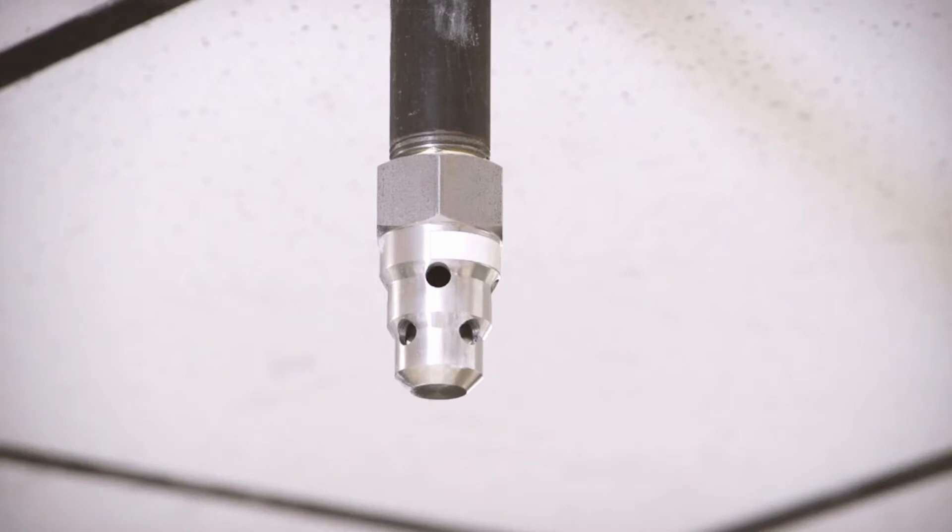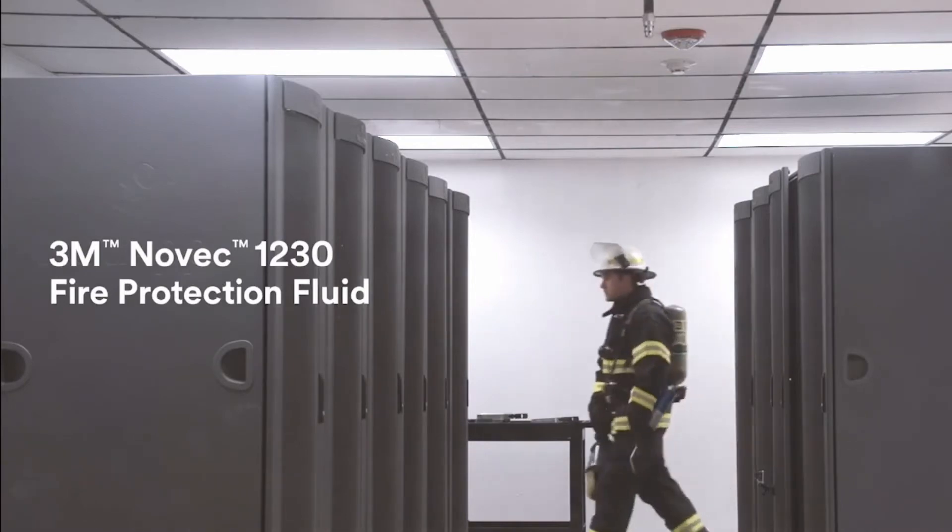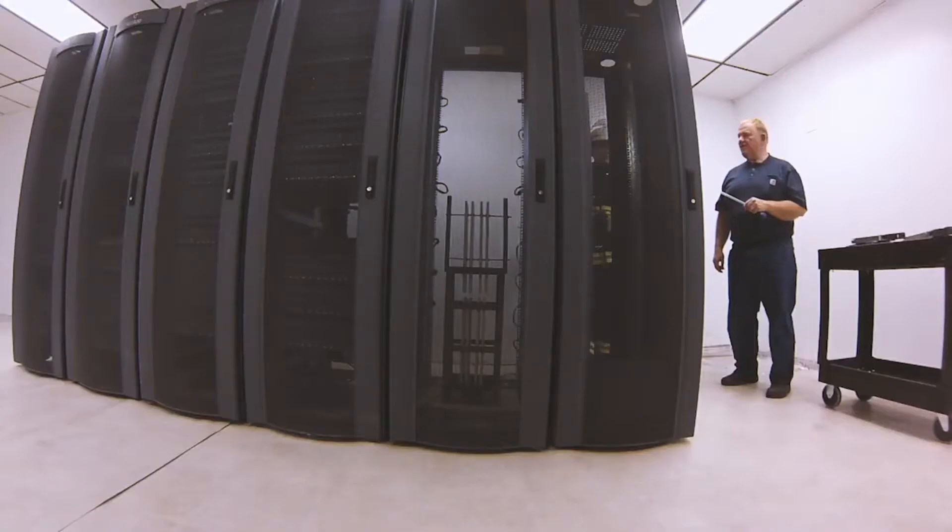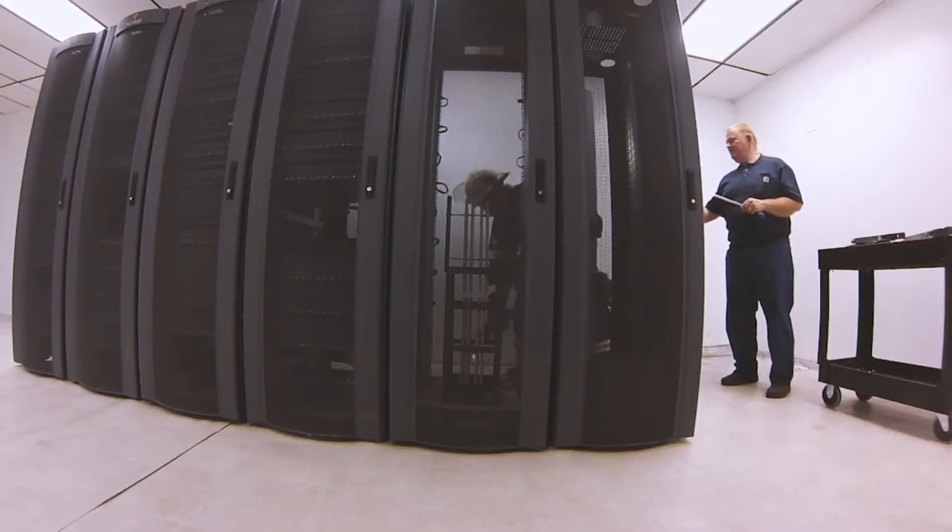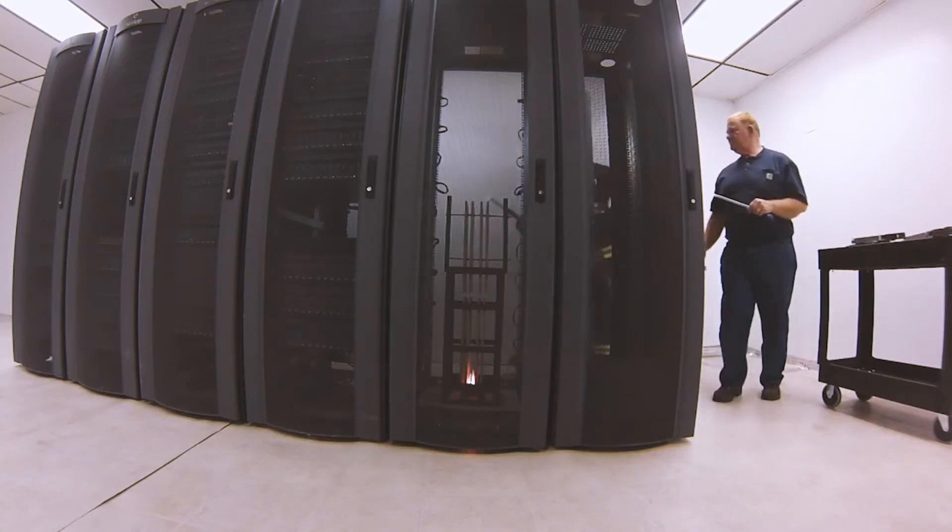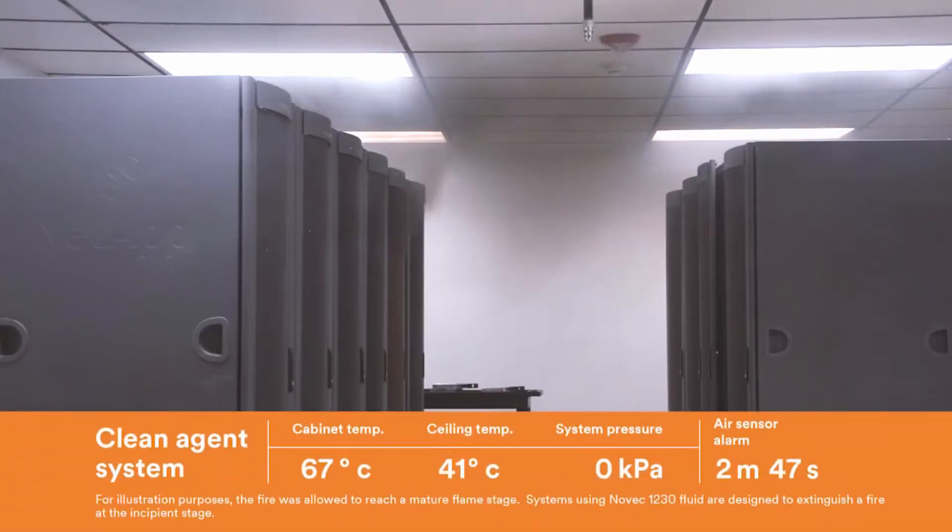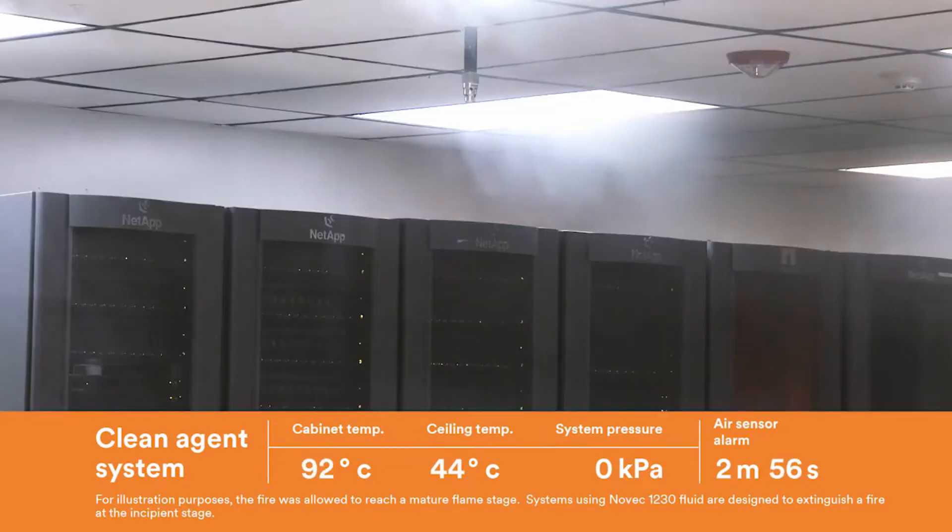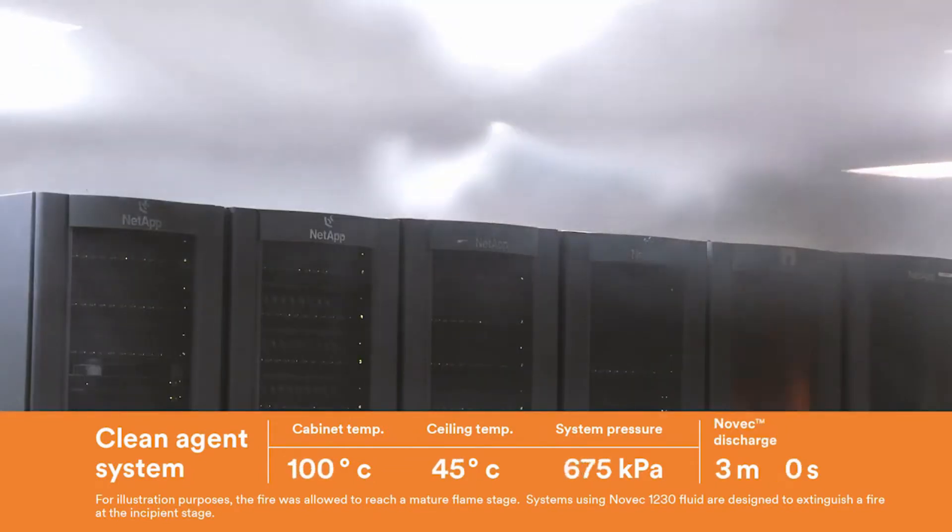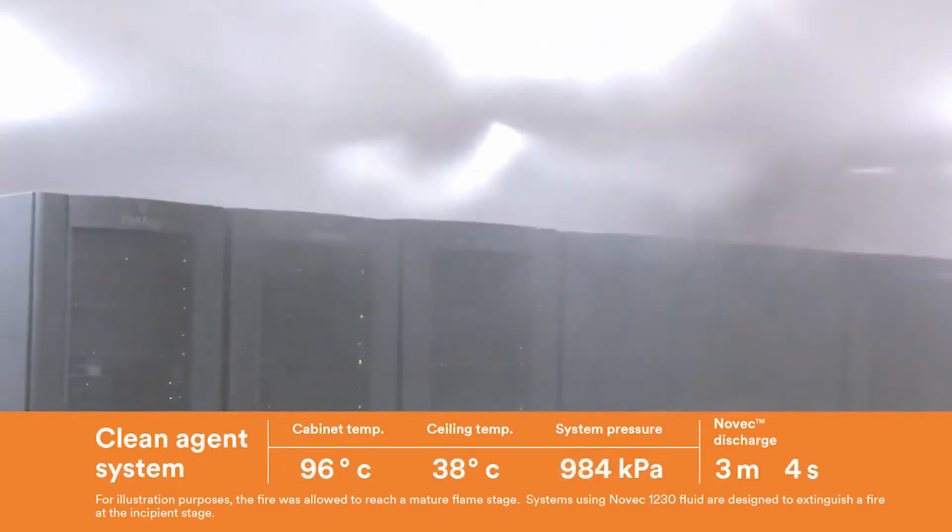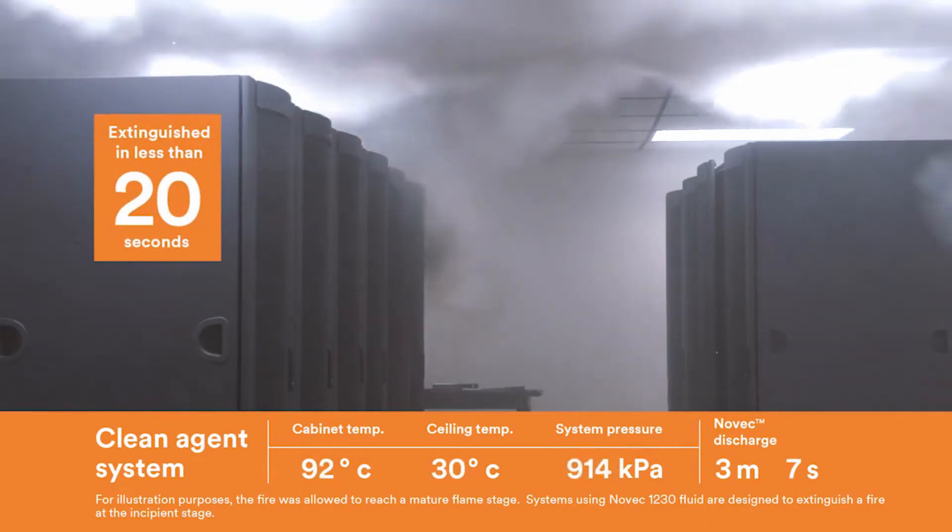A test of the Novec fire protection fluid-based system is run first. To begin the test, a technician ignites sheets of ABS plastic inside an empty server cabinet. As sensors in the ceiling detect smoke and heat from the fire, an alarm is sounded and the countdown to discharge begins. Once the agent is released, it quickly fills the room and penetrates the burning enclosure, extinguishing the fire in less than 20 seconds.